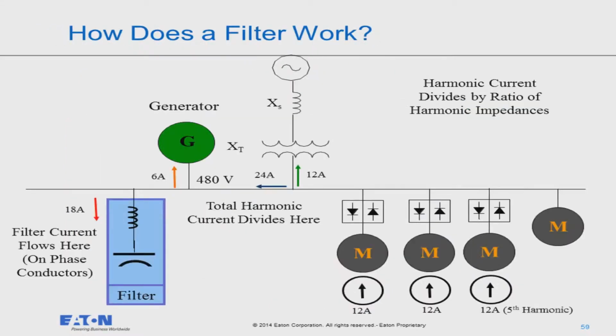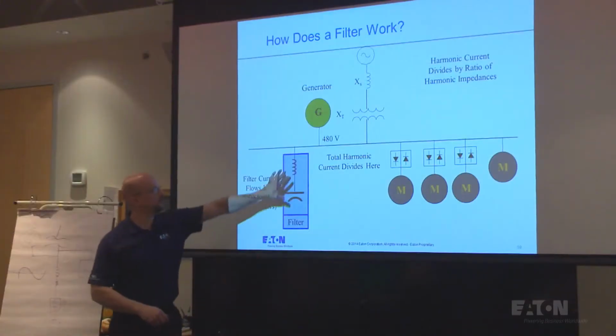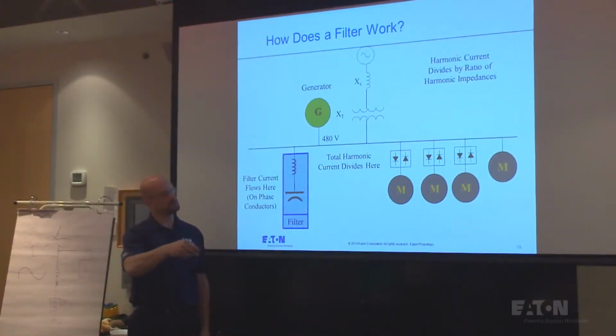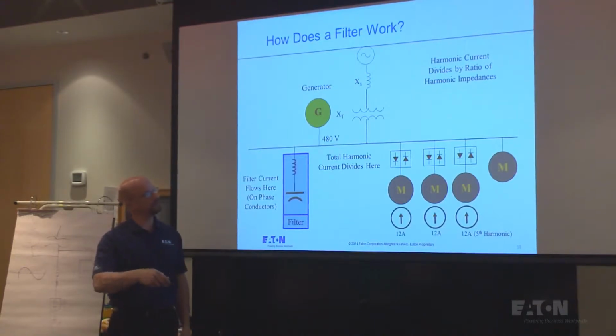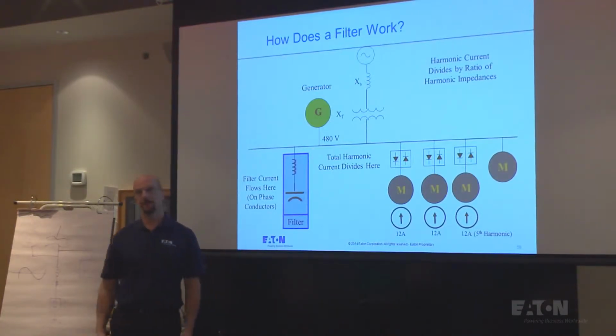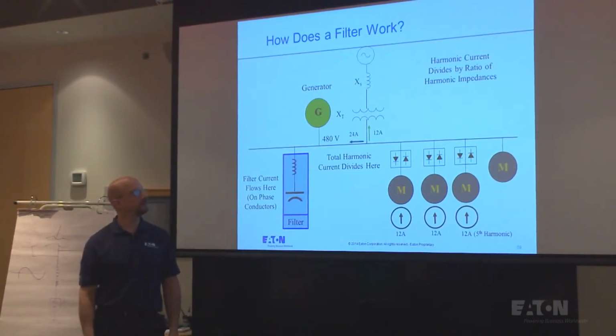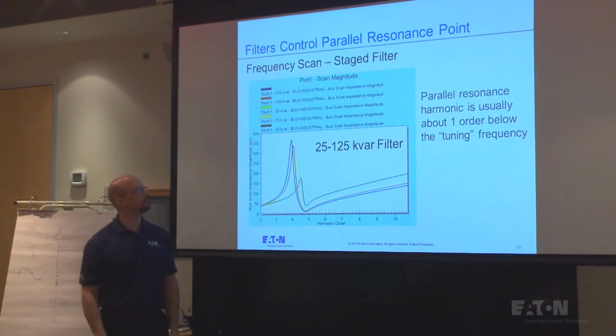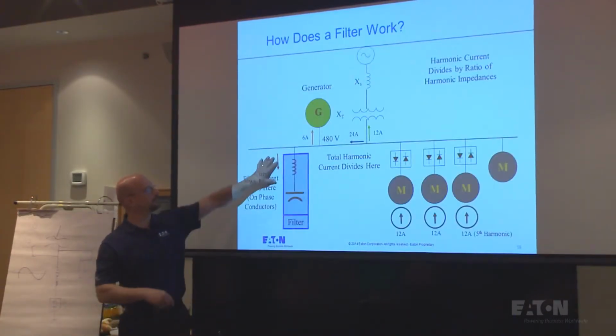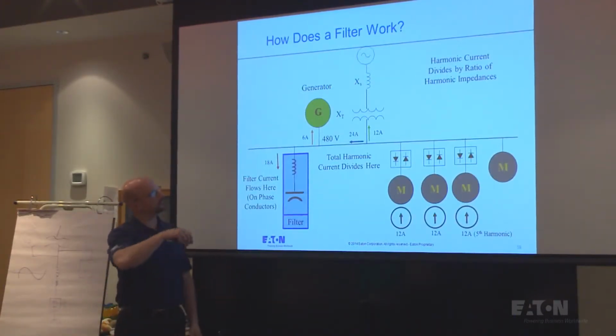How does a harmonic filter work? A harmonic filter, current wants to flow to the path of what? Least impedance, least resistance, right? So if this filter's not here, and these drives produce 12 amps each of fifth harmonic current, all that fifth harmonic current is going up through my transformer or up through my generator, okay? What I'm trying to do with a filter is convince the current to go somewhere else, which is some of it's going to go here, some of it's going to go to the generator if that's online, and some of it's going to go back there.